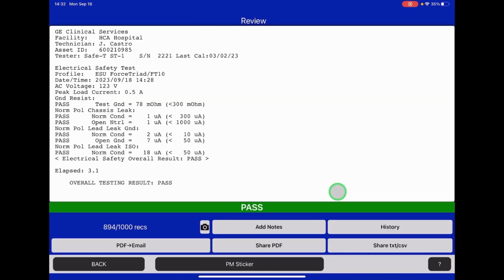So once it's complete, you'll see it goes to the service report, and you'll be able to see all your information here about what testing we did. You'll also see on the safety analyzer itself, if all of the tests pass, the unit will stay green. If any test fails, it will stay red, indicating something is out of range, out of specifications. The same thing on the app. The app will indicate green for a pass, a fail if any one or more tests fails.